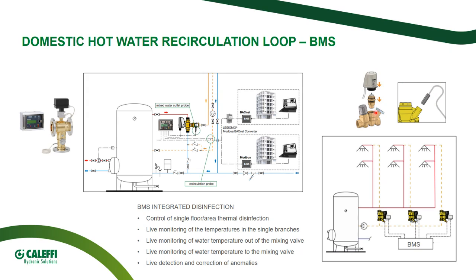It can be done digitally, or we can use the dial on the Caleffi thermal balancing valve. But thermal disinfection, if carried out the right way, is as effective as the chemical one. And moreover, it doesn't have the same undesired effects that sometimes occur with the chemical one. I mean the effect on the water quality, for instance, the chlorine that might affect the water smell or taste, and also the expense caused by the chemicals that have to be stocked, but not for such a long time because they expire. So the managing of chemicals can sometimes be an issue.